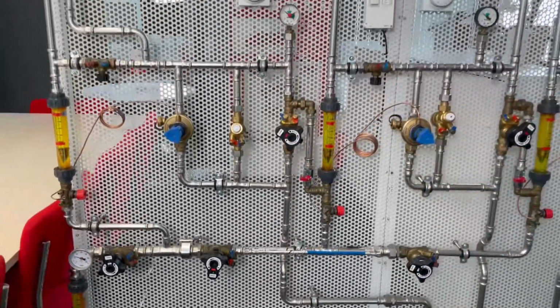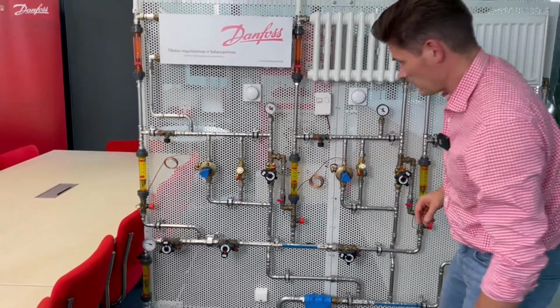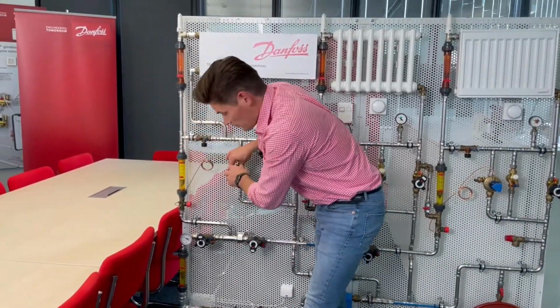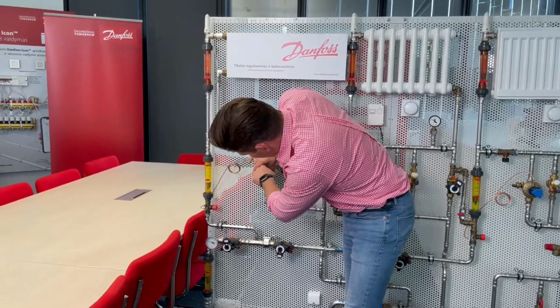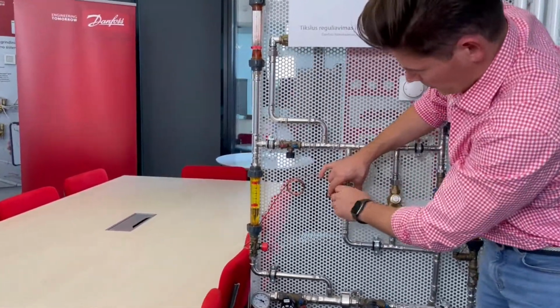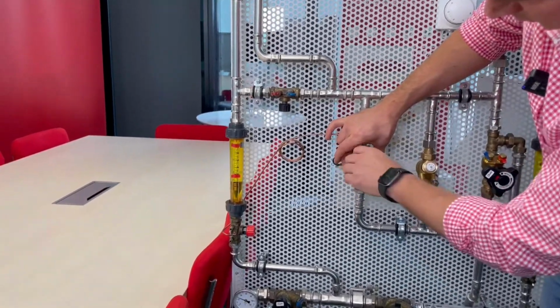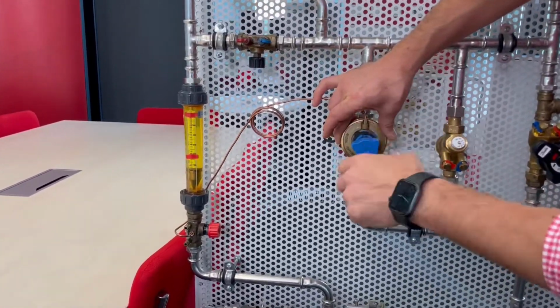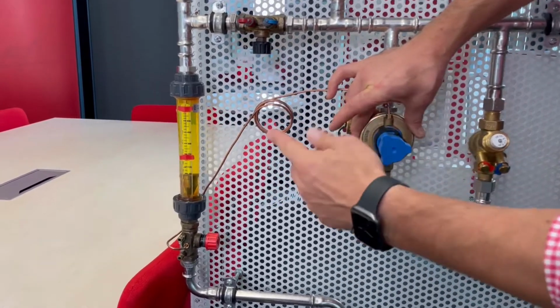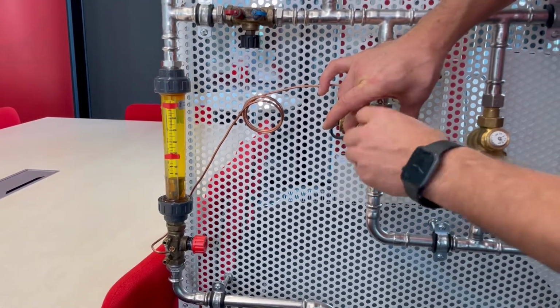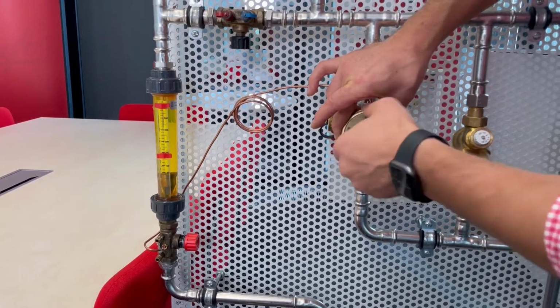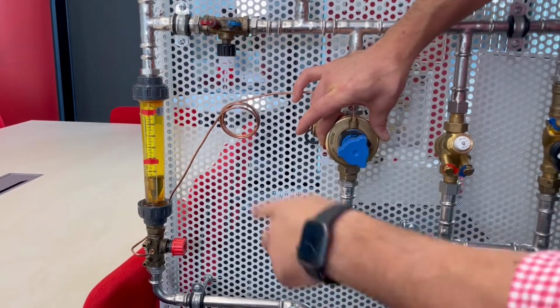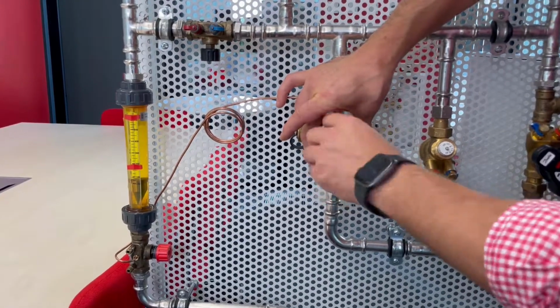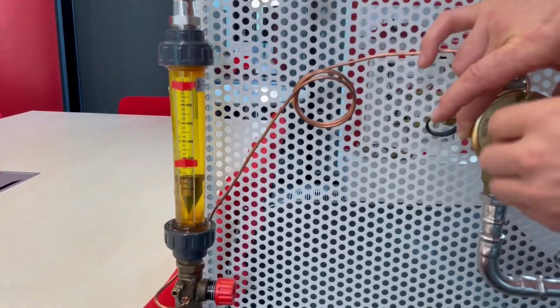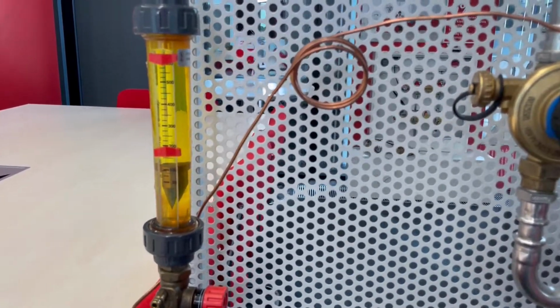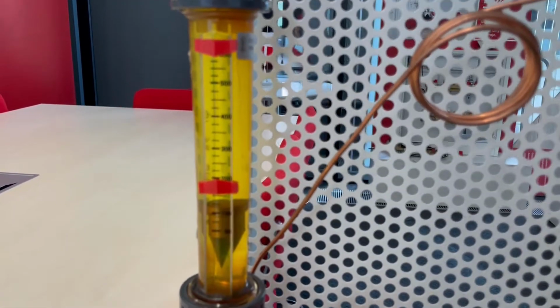We have some kind of different flows. It is not balanced, so I need to balance right now. I can balance with the pressure controller. So I have the possibility to regulate flow with the pressure controller. If I open up, flow decreases, so it works in the opposite way. If I close clockwise, it increases flow. So let's set, for example, 100 liters.